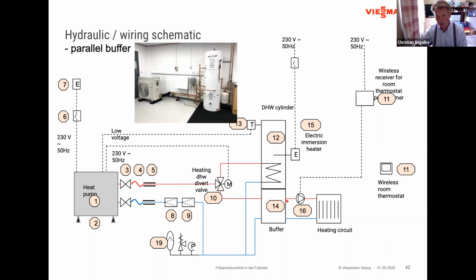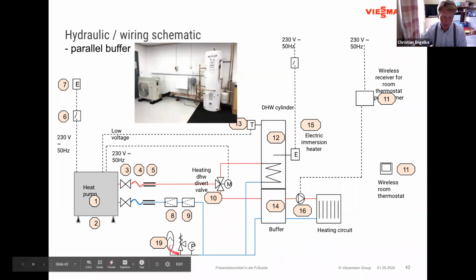From the buffer store, there will be a separate hot water circulating pump to your underfloor heating circuit or radiator circuit, and that circulating pump can be controlled by your room controllers, programmable room thermostats, wireless room thermostats, or whatever is available. And then obviously internally you also need to take care of an expansion vessel, which depends on the water volume you have in the system, and the safety valve.